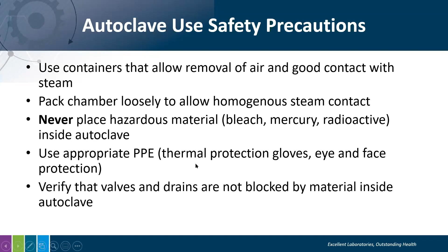That's a huge deal because if people pack an autoclave bag and close the bag tightly, with the pressure inside the autoclave that bag is going to explode or burst inside the autoclave. And then whatever contents you have inside that bag, say gloves or lab coats, paper towel, are going to spread inside the autoclave. When that happens, those materials may clog valves and drains in the autoclave, which can not only damage the autoclave, but also make the process inefficient. Next slide.